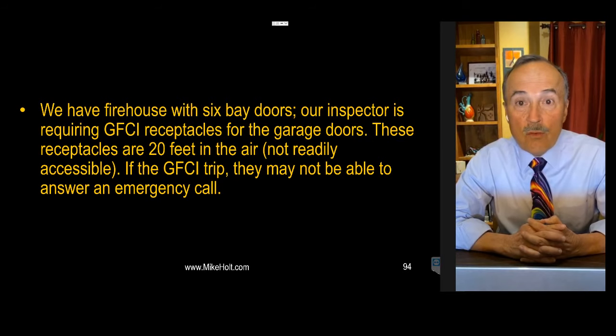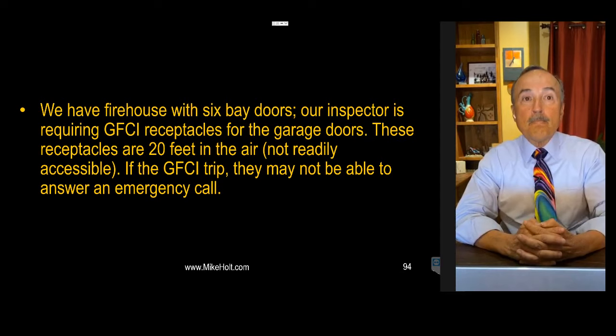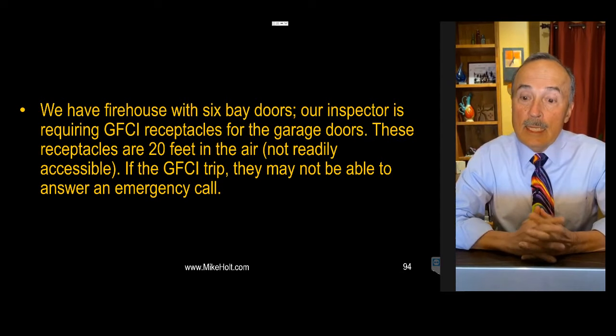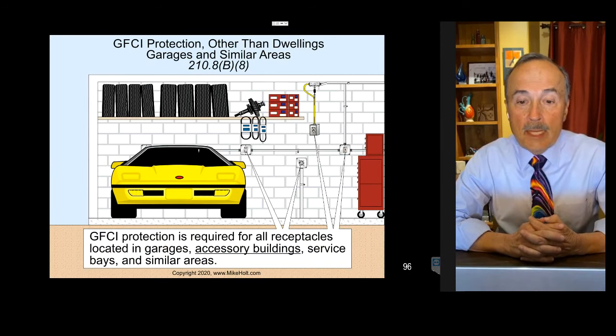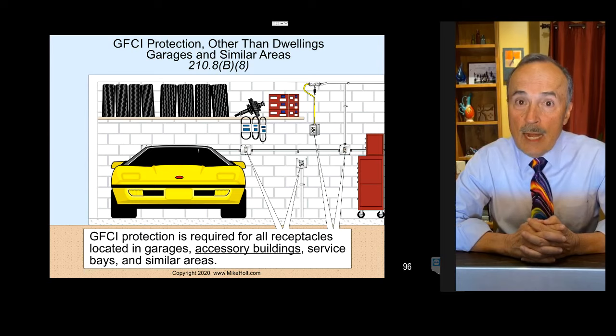Mike, we have a firehouse with 6-bay doors, garage doors. Our inspector is requiring GFCI receptacles for the garage doors. These receptacles are 20 feet in the air. They're not readily accessible. If the GFCI trips, they will not be able to answer an emergency call.